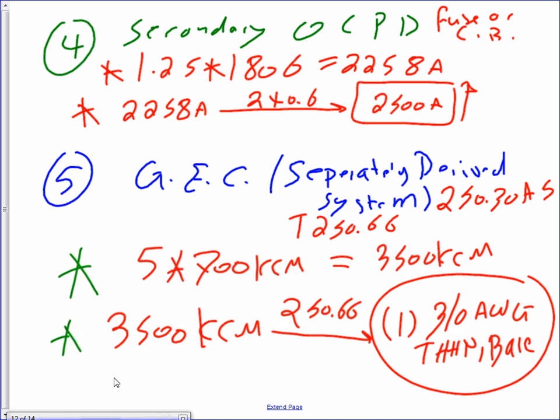Now we need to go to the bonding, the main bonding jumper. Any comments, guys, about number 5? That's the one that goes to the steel of the building, to the ground rods, and what not.